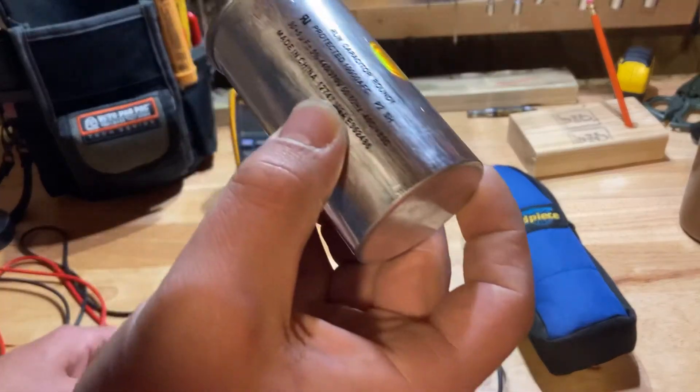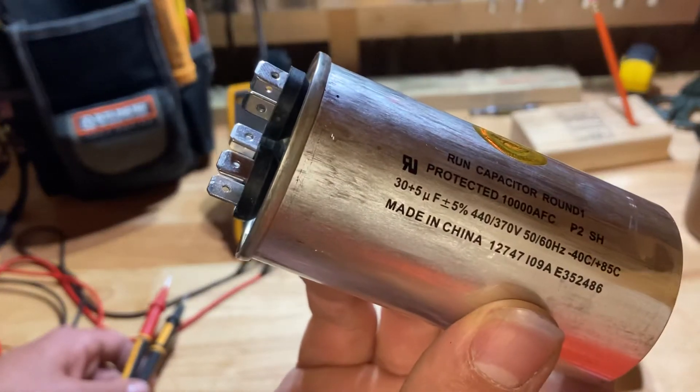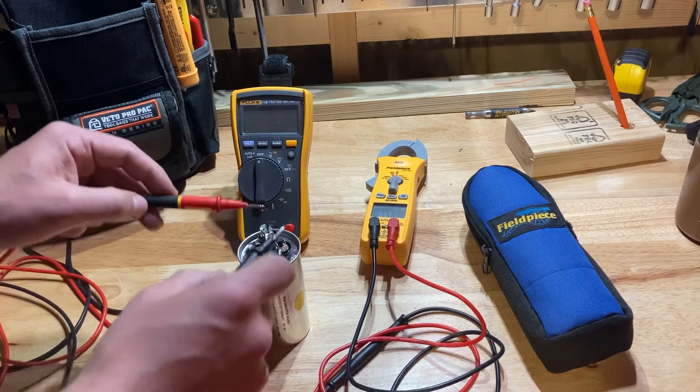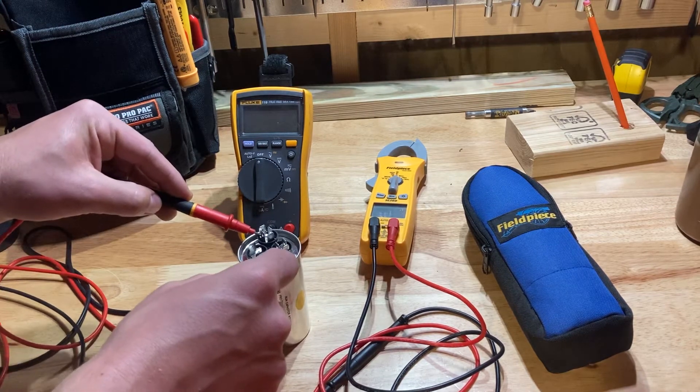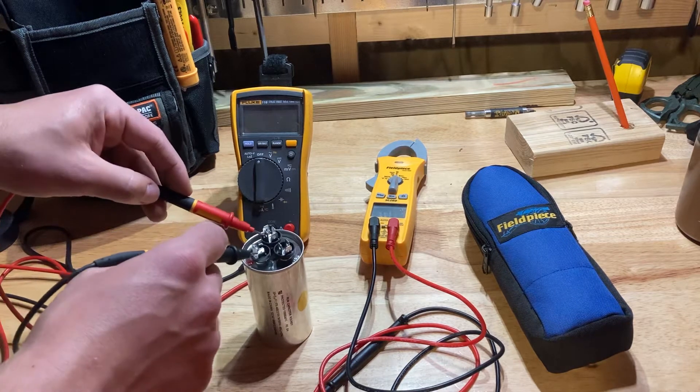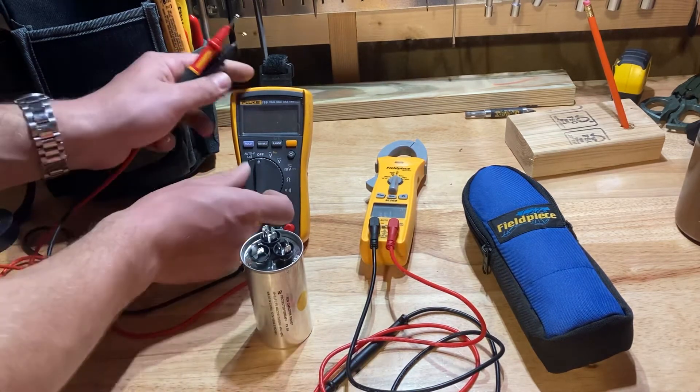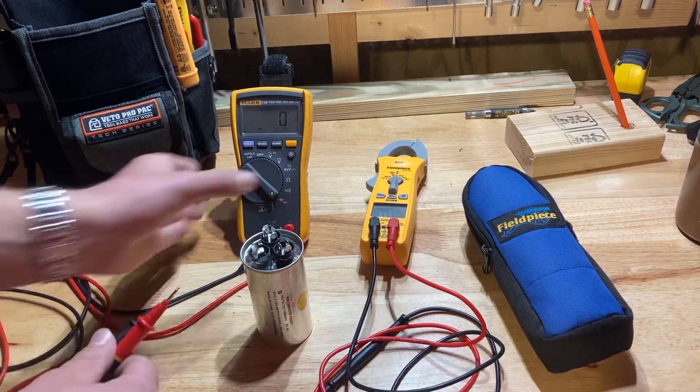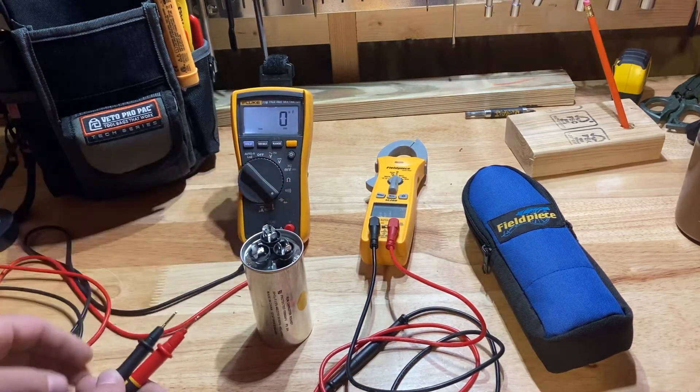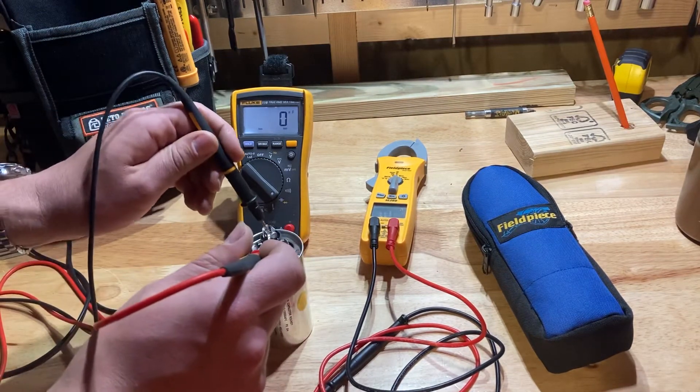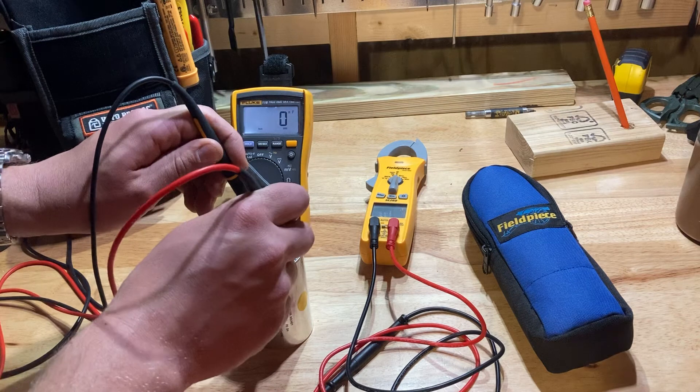If you're using multimeters to test stuff, I would recommend this Fluke way before I would recommend the Fieldpiece. I'm going to test this capacitor. This is a 30 plus 5. So from the common to the herm we should be getting 30 microfarads, and from the common to the fan we should be getting 5. I'm going to turn it to microfarads and you can see that screen good. We're going to go common to herm.